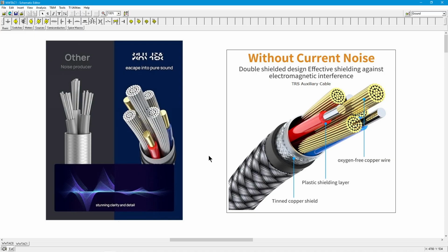All right. The best thing, if you could get a combo, if you could get a shield that will give you 100% shield with a foil, and then maybe have a spiral wrap or a braid around that, right? That would give you a lot of strength. You'd have 100% coverage. You'd have the best possible common mode rejection out of there. All right. But the thing that really sticks in my eye here, it's almost like getting an arrow in your eye, is first of all, the number of conductors and the different types. So this, if you look at it, is pretty much the same as this.